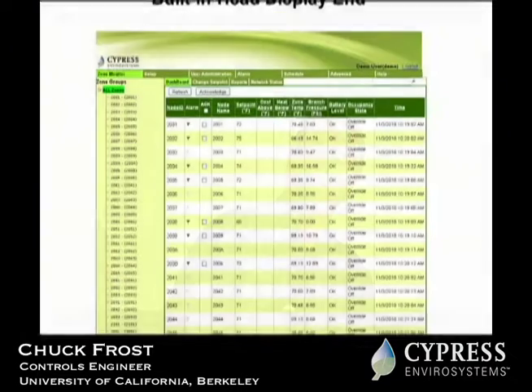If you don't have a front end, a DDC system, or a building automation system — whatever you want to call it — this is their server. Looking at the server, you can get some data: what your set points are if you're communicating with a particular thermostat. If you don't have any control system or DDC and you're not interfacing it, this is what you would use to look at it and change your set points, night setback, and things like that.